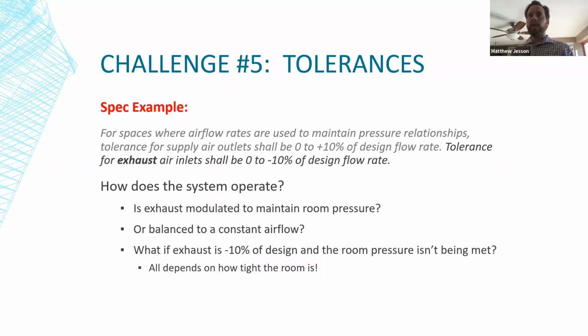So typically that requirement is really driven by how tight the room is built, something that we all have very little control over. So this is one that typically, as the balancer, I would discuss with the engineer to determine, okay, if the goal is to get this room to a pressure of positive 0.02 inches, how far down can I go with the exhaust? Can I go to half of its design flow rate if needed, or lower, or is there an absolute minimum exhaust that we need to maintain? And if it gets down to that point, do they need to look at taking further measures to tighten up the room to meet that room pressure?